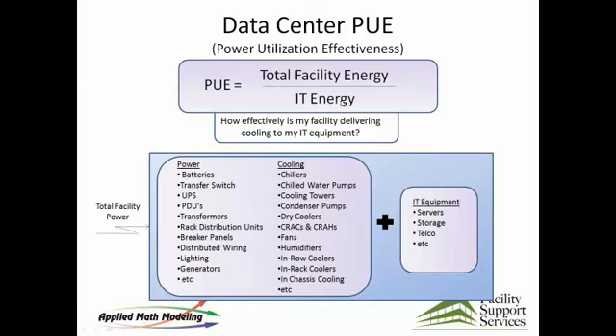By looking at just this set of numbers right here, you can get a lot of information about what's going on in your data center. I can see that our PUE is awful. Our energy contribution here, our ratio, is awful. RTI is well below where it should be, by 40 points. I've got hot spots in the room, and I've got a lot of cold spots in the room. The cost to run it, assuming in this case 10 cents per kilowatt hour in the calculation, would be $275,000 a year. And if we take a look at the CRACs, you see they're set pretty cold, down at 56 degrees, 58. These are measurements that Matt made.